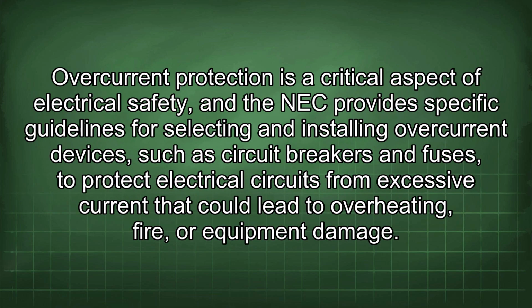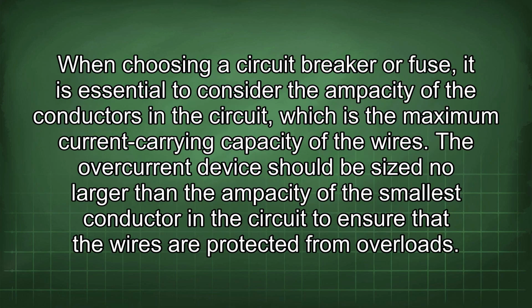Overcurrent protection is a critical aspect of electrical safety, and the NEC provides specific guidelines for selecting and installing overcurrent devices, such as circuit breakers and fuses, to protect electrical circuits from excessive current that could lead to overheating, fire, or equipment damage. When choosing a circuit breaker or fuse, it is essential to consider the ampacity of the conductors in the circuit, which is the maximum current carrying capacity of the wires. The overcurrent device should be sized no larger than the ampacity of the smallest conductor in the circuit to ensure that the wires are protected from overloads.